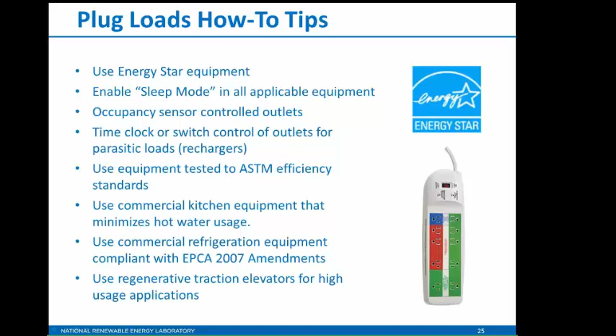Elevators are also a hidden load. Many hydraulic elevators require the oil be maintained at certain temperatures, which is a constant parasitic draw on the system. Using regenerative traction elevators is one way to save that energy. In fact, in a regenerative elevator, rather than using electric resistive braking, that energy gets dumped back into the building's electrical grid for use elsewhere.